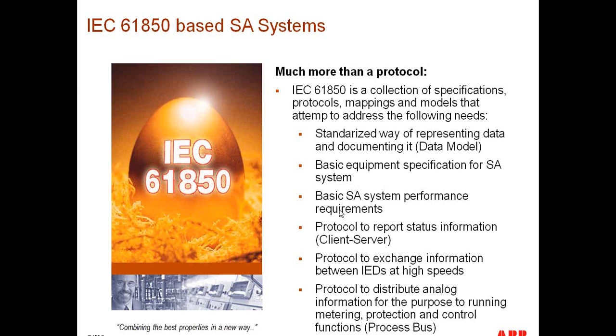So in the case of protection and control applications utilizing GOOSE messages, this is something that is quite relevant. The standard defines that a GOOSE message should take X amount of time. Just as a manufacturer of an ice cube relay, which are typically found in output contacts of protective relays, can tell you the travel time of that particular output contact. So the standard, instead of leaving it up to the manufacturers to define that, defined it. And since all of these requirements are defined, we can have tests that we can follow, and end users and consultants can have the confidence that if a particular piece of equipment is tested or is deemed to be IEC 61850 compliant, it meets all of these different requirements.